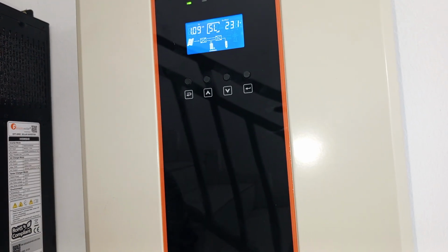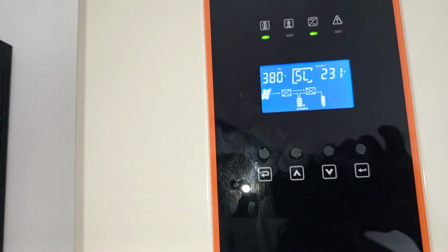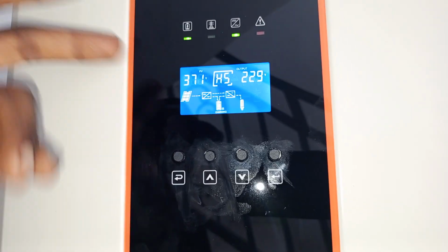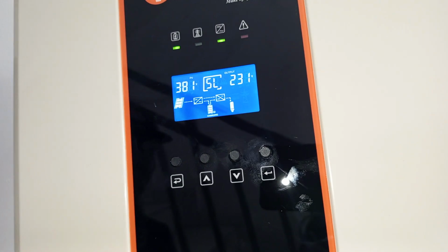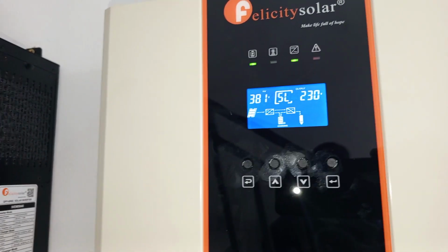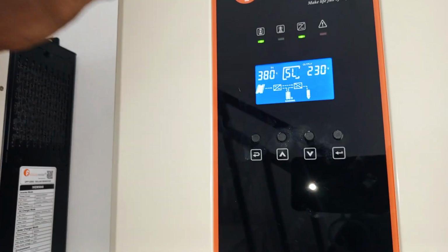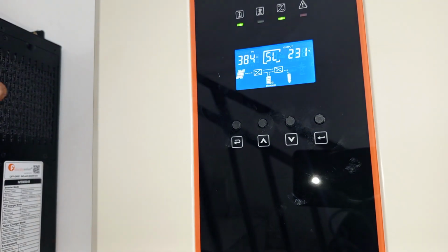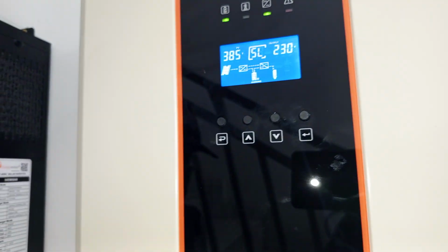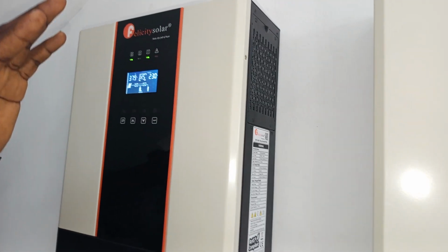Secondly, what is your PV generating? My PV is currently generating about 1.9 kilowatts. Okay, what about the voltage you are able to achieve from your PV? Since I connected in series, I was able to get 370, 380 volts, but when the sun is high, I'm supposed to see 430 volts. Today is not sunny, that's why it's not generating as much voltage as expected. The position of the panels also matters. Even if there is sunlight, this one will generate more compared to that one, because this one is facing south and that one is not, because of the way the roof is. So we just have to manage to get our system installed.